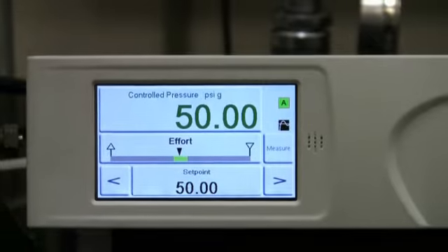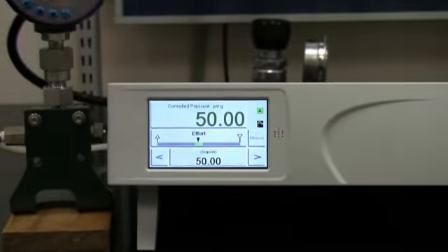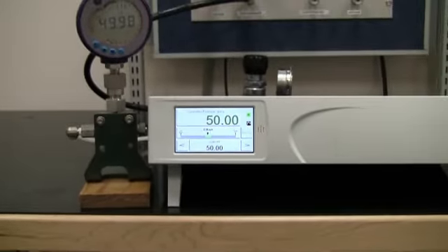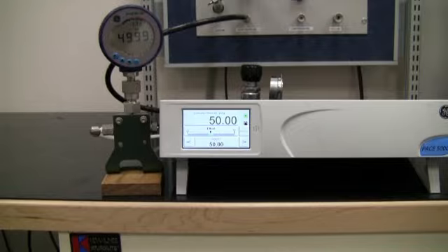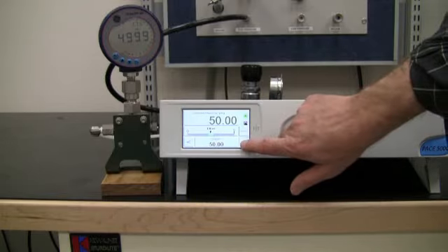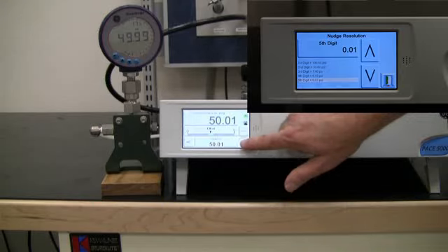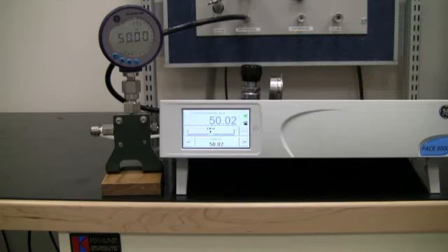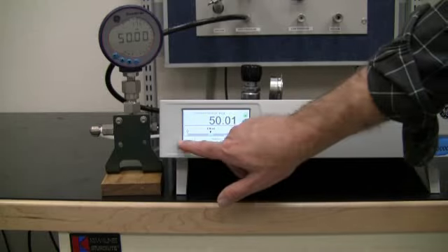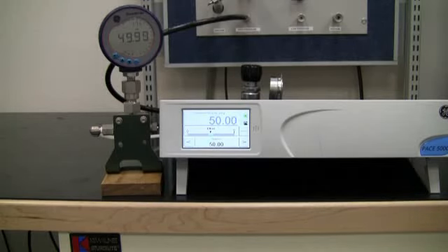We will now zoom out so we can see the pressure displayed on the device under test. If we prefer to be at a cardinal pressure reading on the device under test, we can use the nudge arrows to increase the pressure by a user-defined magnitude. In this case, we set it to 0.01 psi. We can select the right arrow to nudge the pressure up so the device under test displays exactly 50.00 psi, and then compare this to the reading on the PACE5000. The left arrow allows us to nudge the pressure in the downward direction.